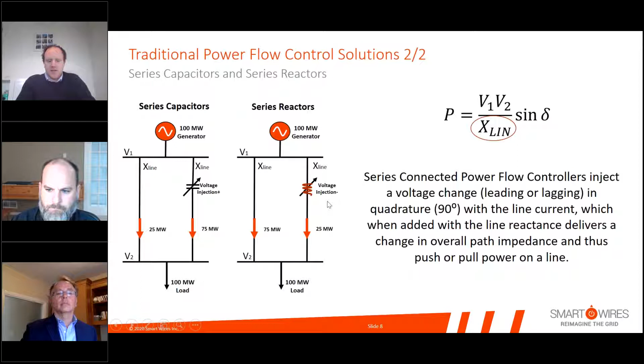Physically, what these look like: a series capacitor, both of them are insulated from ground, so they're installed at line potential or line voltage. Traditionally, series capacitors have been installed on extra high voltage circuits. In Canada, we see them quite often connecting large hydro dams in the north with load centers in the south, which brings those two areas electrically much closer together.